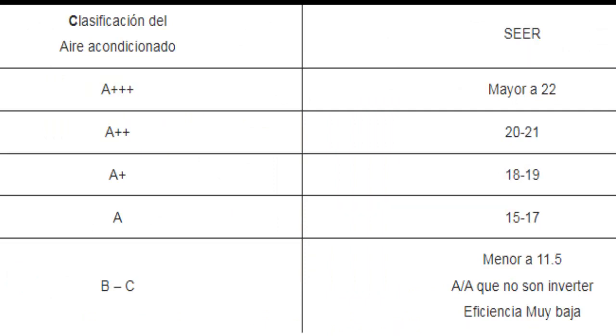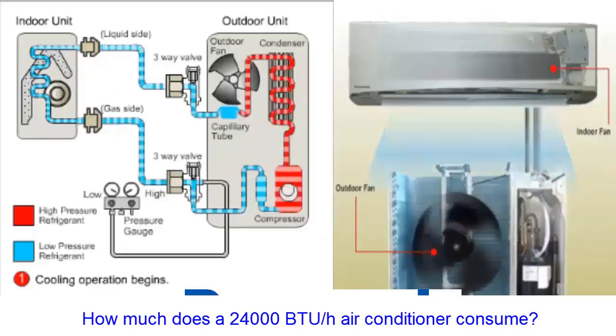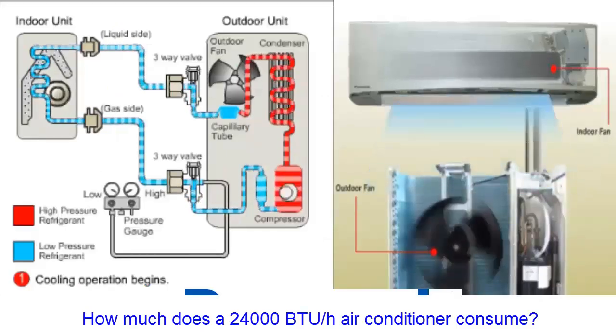To calculate this average current value, knowing the SEER — Seasonal Energy Efficiency Ratio — value is necessary. The SEER parameter is measured under various working conditions, with the same room temperature, but varying the outdoor ambient temperature from 18 degrees Celsius (65 degrees Fahrenheit) to 40 degrees Celsius (104 degrees Fahrenheit).